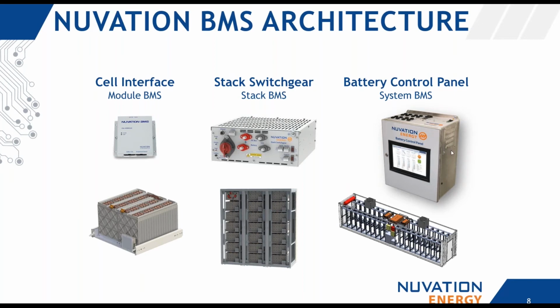And our battery control panel, which is relatively a new release for us, intelligently manages these multiple stacks that are connected to a parallel common DC bus. So they allow large ESS systems to be put together without having to code up and verify how the different stacks interoperate.